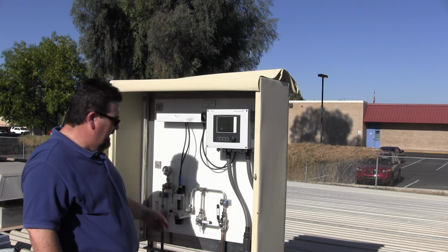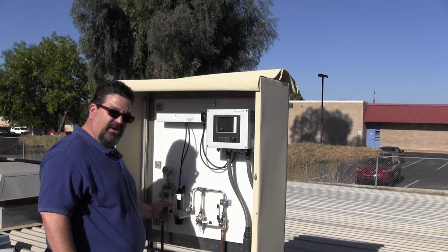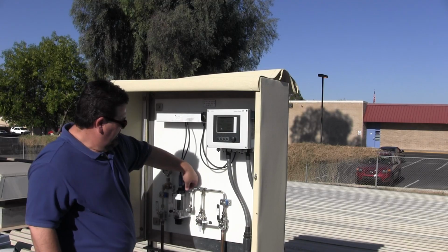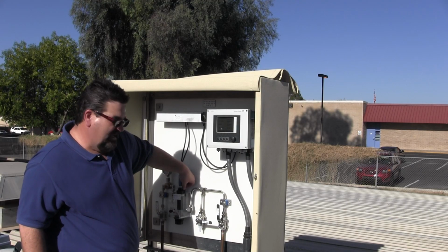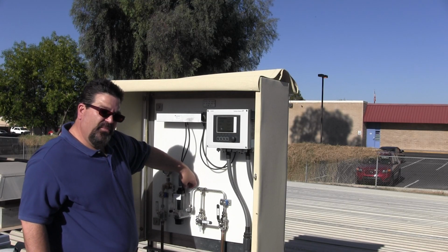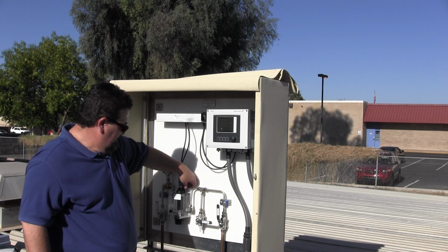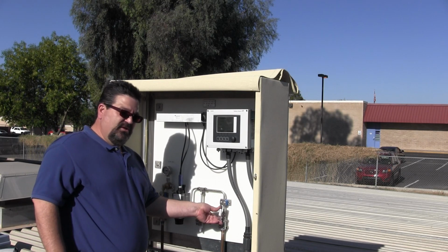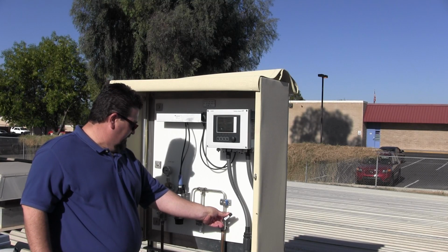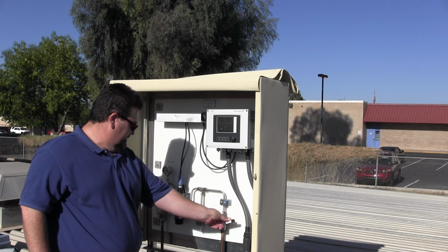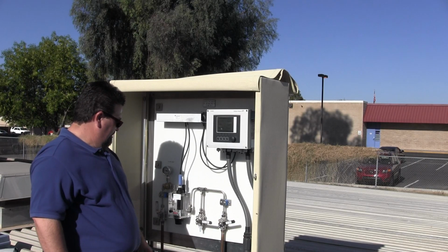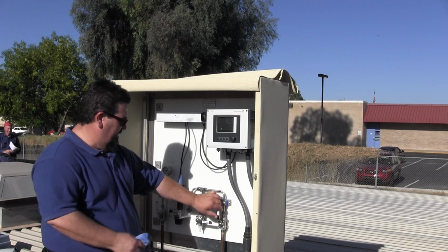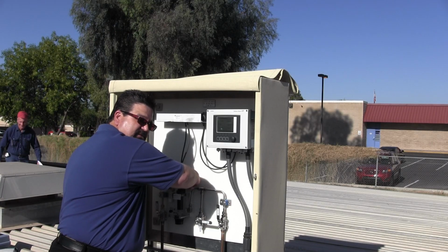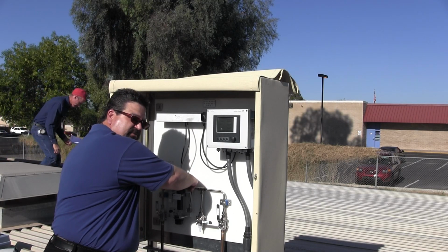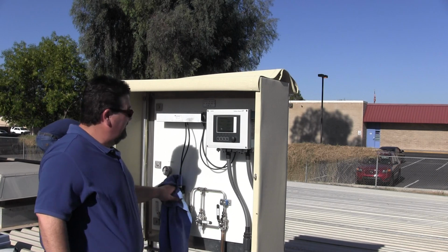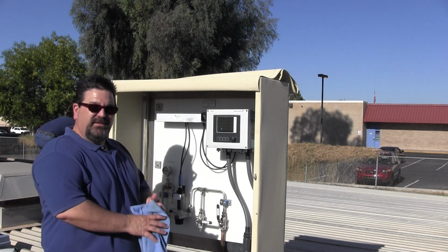Now we verify we have a sample flow. It's not uncommon to have some air bubbles in here after you've done a calibration. This small hand valve on the back is to release that air. I'll open it about 3 or 4 rounds. And then I'll usually just close the outlet valve slightly, which will back up some pressure in the flow block and push the air out. Once I've pushed all the air out, open the outlet valve, hand tighten the air release. Hand tighten only. It has 3 O-rings on it. There's no need to over tighten. That completes the pH calibration.